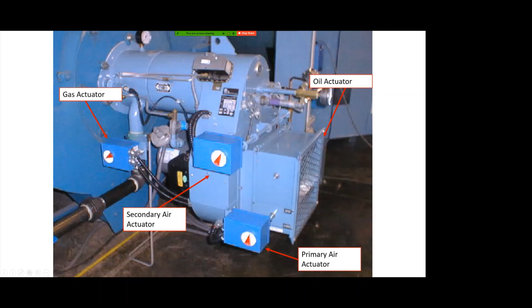So those control links actuators that you saw on the previous slide have now been replaced with our Slate actuators. These actuators communicate via Modbus to the fuel air ratio control module. As you see up top, we have varying torque specs on the actuator, so we can accommodate really limitless requirements for our fuel and our air ratio valves, right? Obviously, the more air we're moving, we need a little more torque. So we start off with 50 inch-pounds, 150, 300, and 900, right?